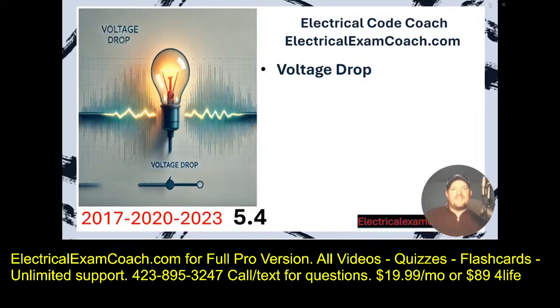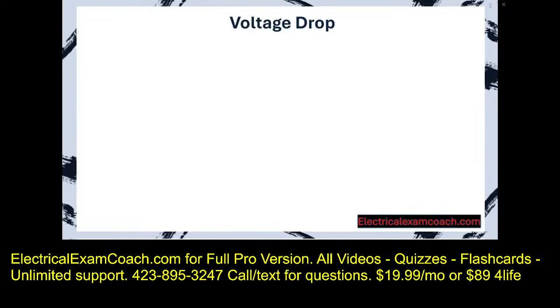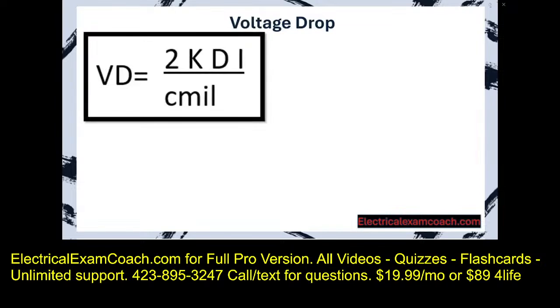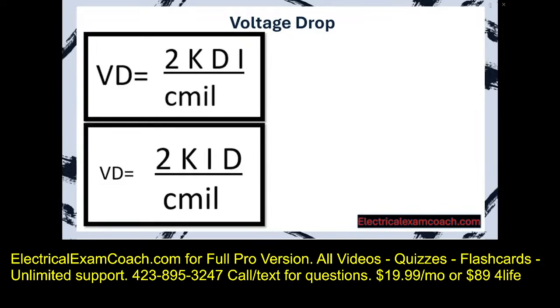Let's get to it. If you were to do an internet search for a voltage drop formula, you would likely find this one right here. Voltage drop equals 2KDI over cmil. And that is an excellent formula. And it's actually the one that I use. But I've rearranged it so it's easier to remember. I do it like this.